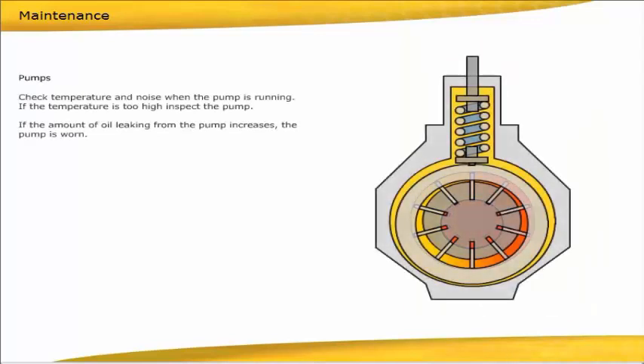Pumps: Check temperature and noise when the pump is running. If the temperature is too high, inspect the pump. If the amount of oil leaking from the pump increases, the pump is worn.